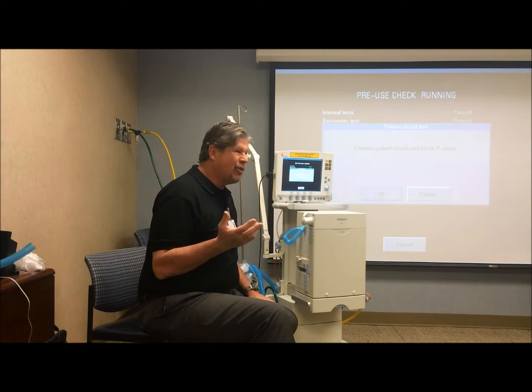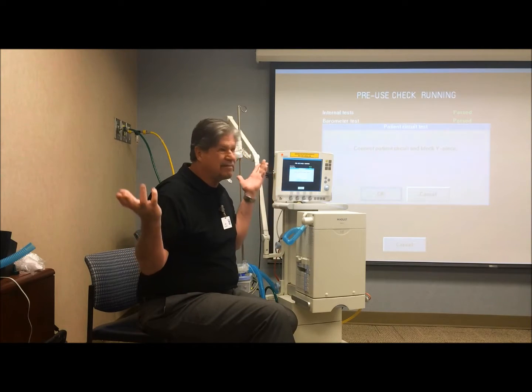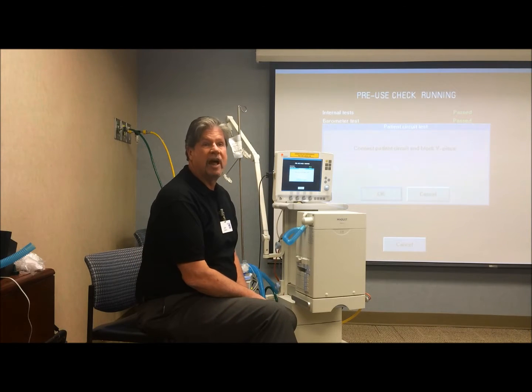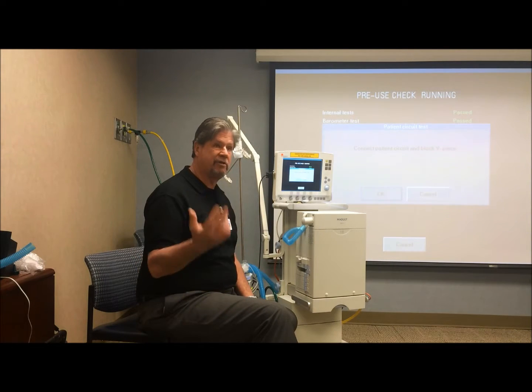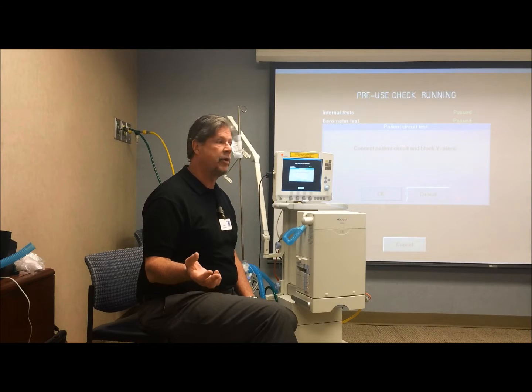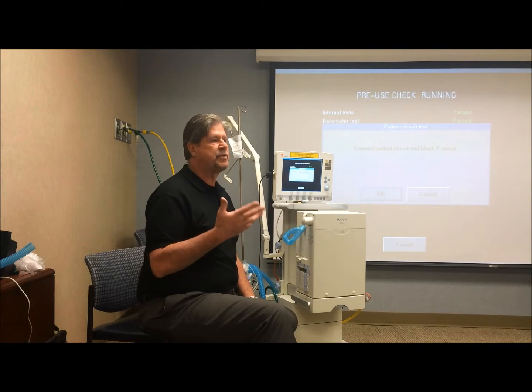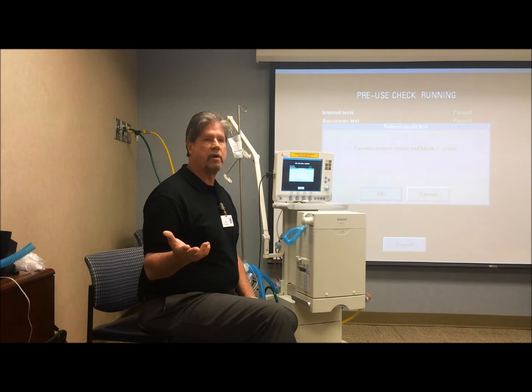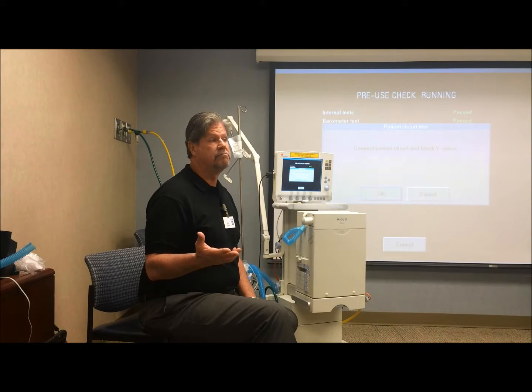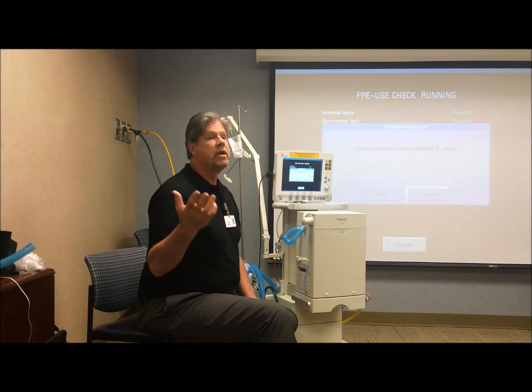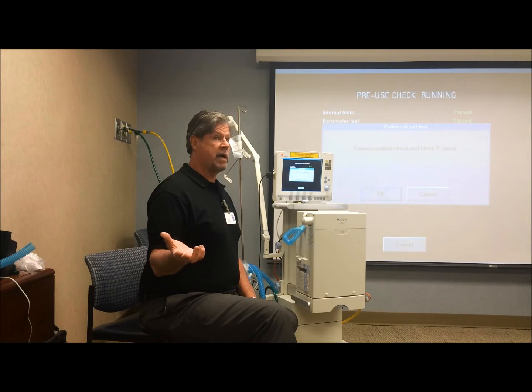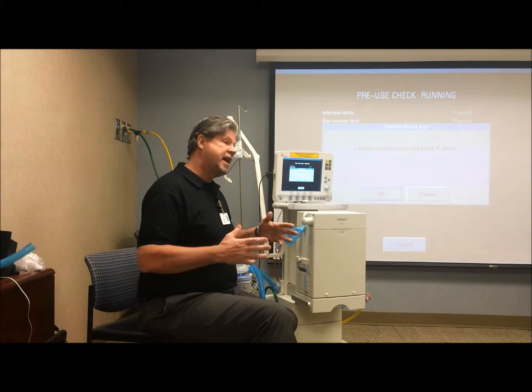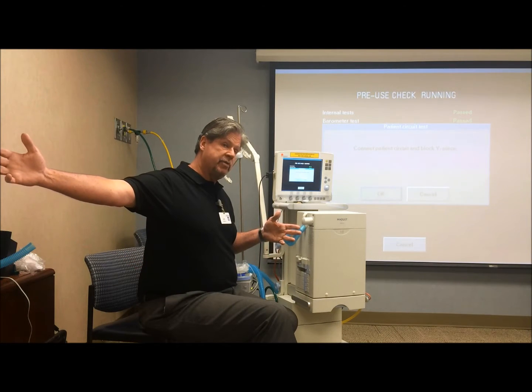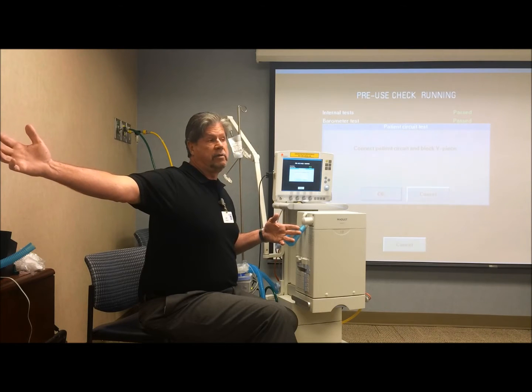Now, in the adult world, 50 cc's, I'm pretty sure, is not going to matter a whole lot, particularly when you're delivering a 500 or 600 cc tidal breath. But when is this particular test very important in the adult world? When you're taking the ventilator to the MRI. So when you go to the MRI suite, you put on a double circuit.